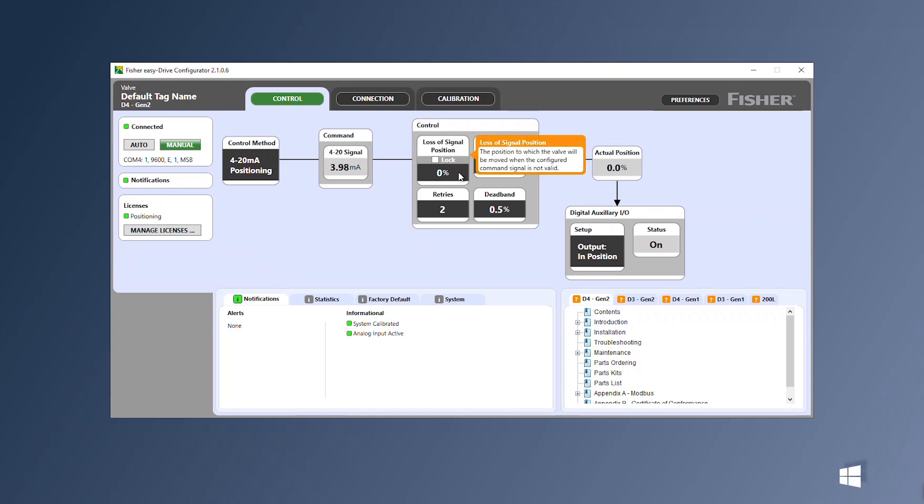The loss of signal position determines where the valve will move to if the input signal drops below 3 milliamps.